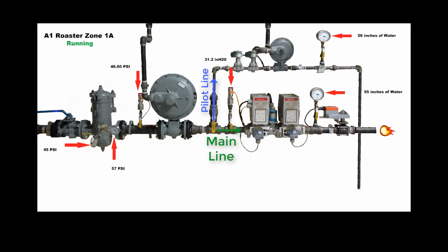In the main line, a venting valve exists between the main and blocking valve in order to prevent gas buildup. Then, the gas flows through a pressure meter to monitor the output pressure and then passes through a control valve, which is actuated by a 4 to 20 milliamp signal. The gas is then ignited by a spark.